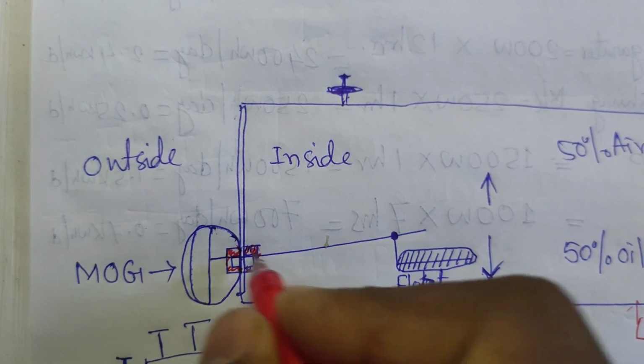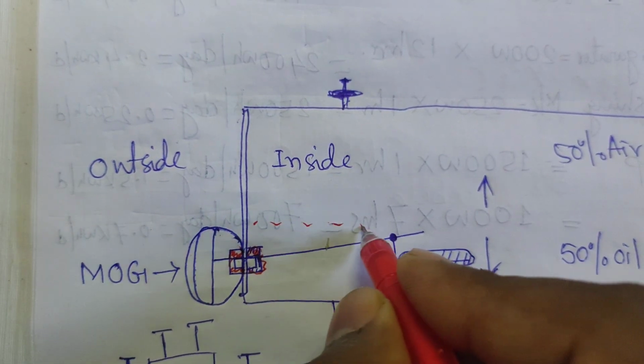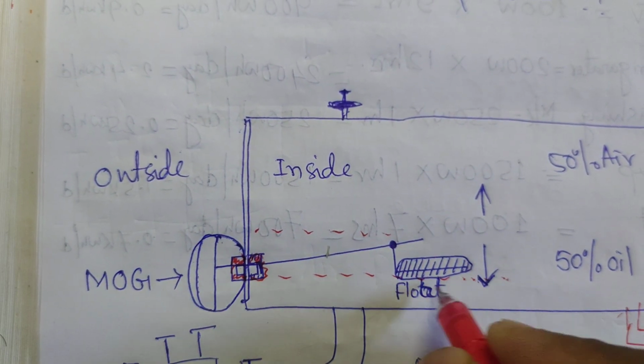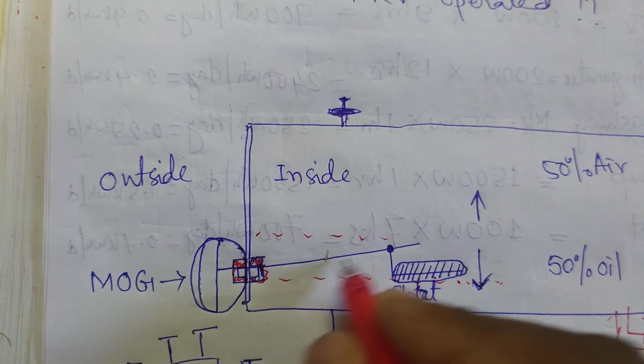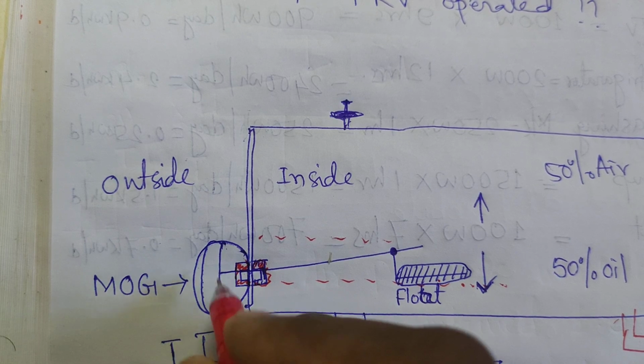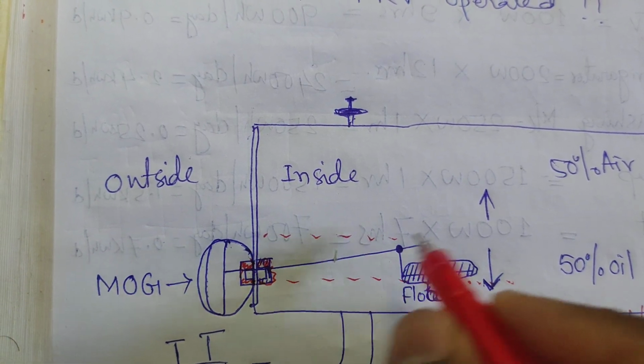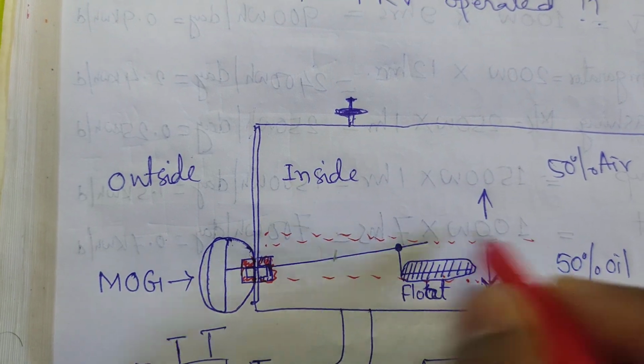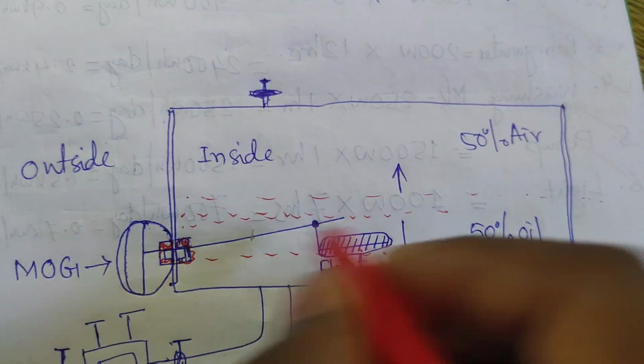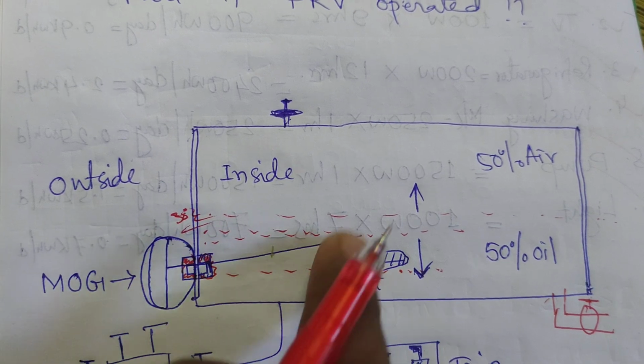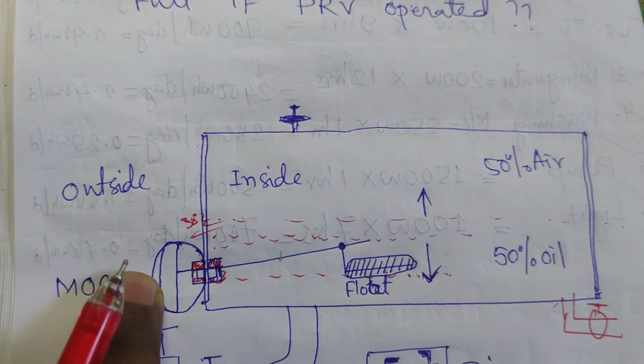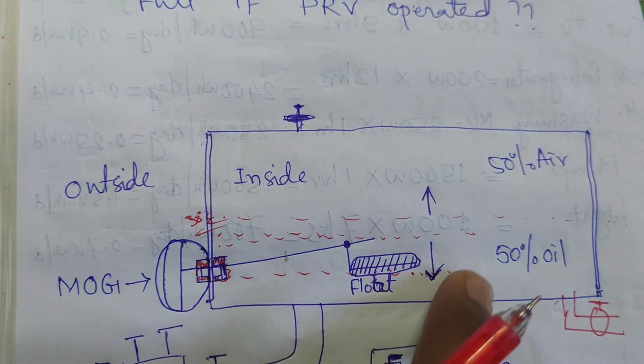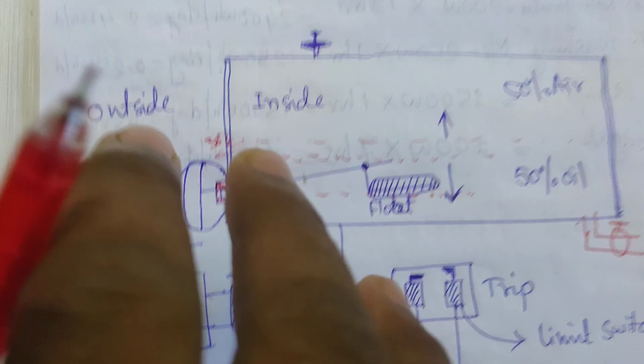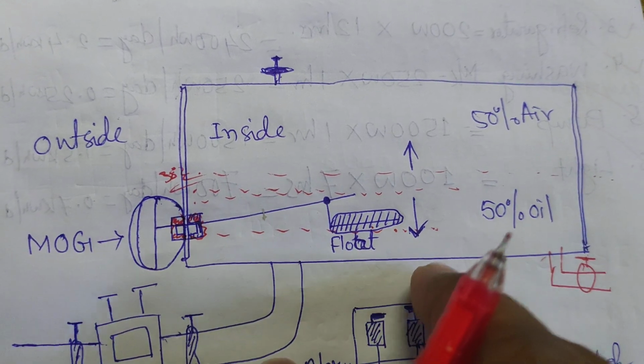This inside and outside magnet, as per the position of the oil, if the position of the oil is this, the float will be here. As per the position of the oil, the dial will be shown. If you are filling the oil on the upper side up to half, or up to 30 degrees Celsius, that means this is the 30 degrees Celsius, so the float will be on the upper side and the 30 degrees Celsius indication will be shown here. So 50% must be air and 50% oil here, for the transformer conservator.